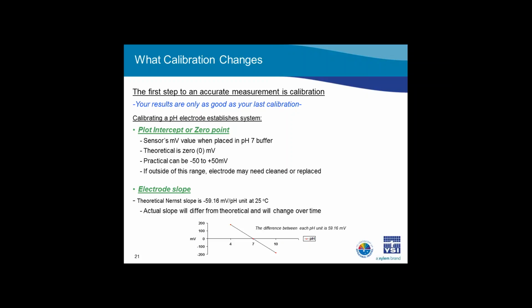So, what are we actually doing when we perform a calibration? Chris previously discussed that we calculate pH based on the established linear relationship between pH and the sensor's millivolt output, as defined by the Nernst equation. In order to apply this relationship to the electrode's output, the instrument must be calibrated properly using buffers of known pH values. During the calibration, the sensor's millivolt values and the pH buffer values are used to establish the electrode slope and intercept, or sometimes referred to as zero point or offset, of the plot of millivolts versus pH. Once the system has been calibrated, the millivolt output of the electrode in any media can be converted by the instrument software to a pH value. We will define the practical limits of the zero and slope again later.